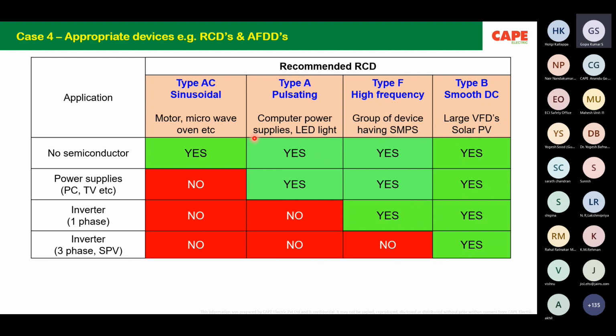Case number 4. We use RCDs as a protection against direct or indirect contact. So the situations are very much explained in the standard. Now, what is important in the new IEC is the type of RCDs for typical applications. There are 4 types of RCDs available: type AC, type A, type F, and type B.